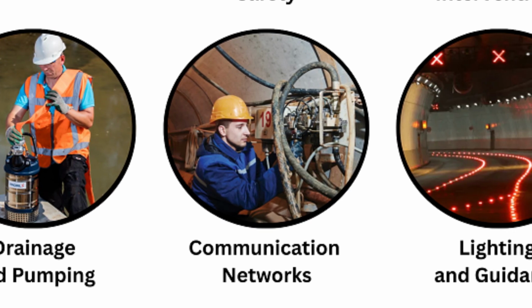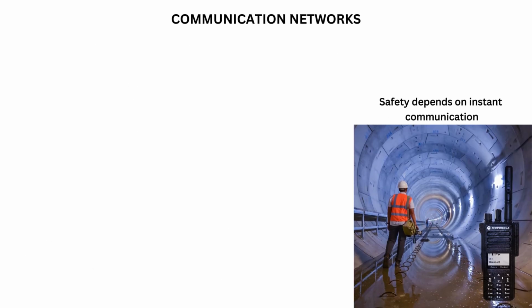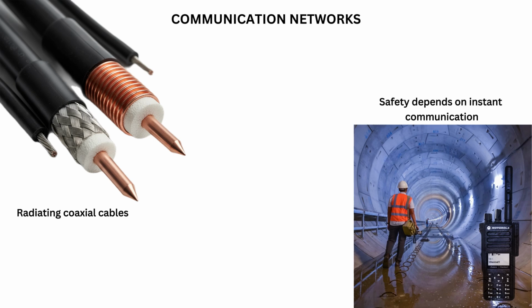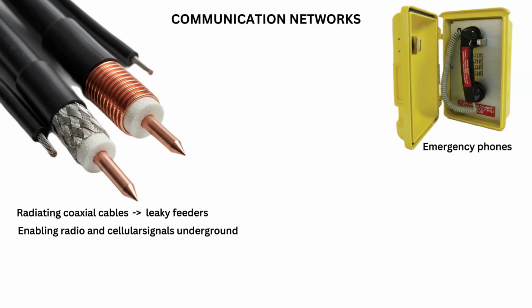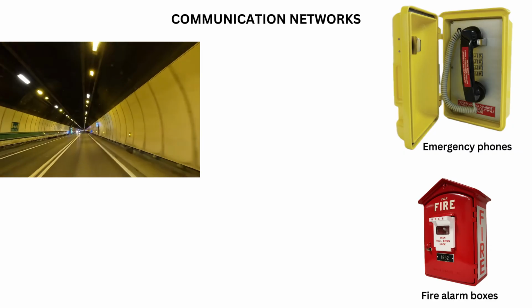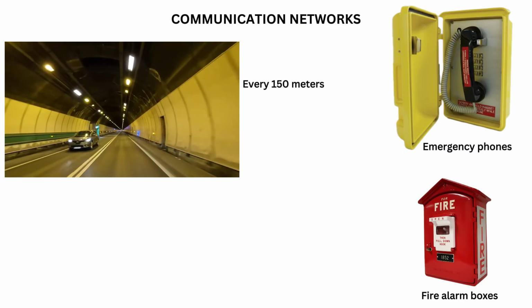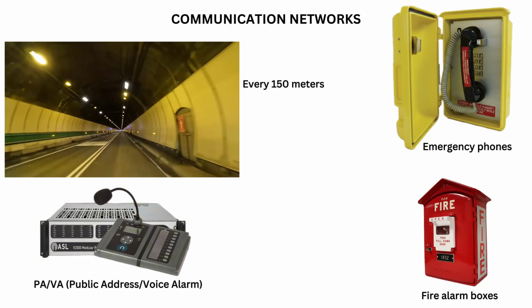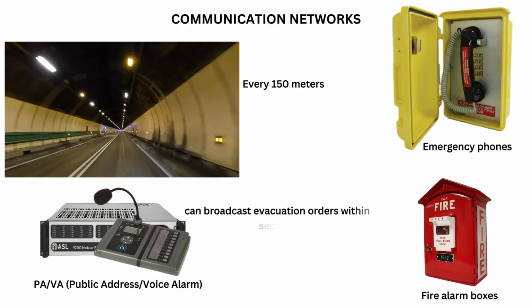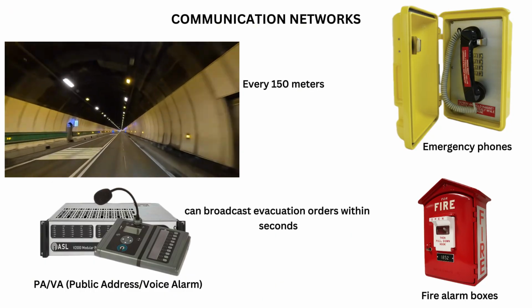Communication networks. Safety depends on instant communication. Radiating coaxial cables, also called leaky feeders, act as continuous antennas, enabling radio and cellular signals underground. Emergency phones and fire alarm boxes line the tunnel every 150 meters. PA/VA, public address, voice alarm systems, can broadcast evacuation orders within seconds.